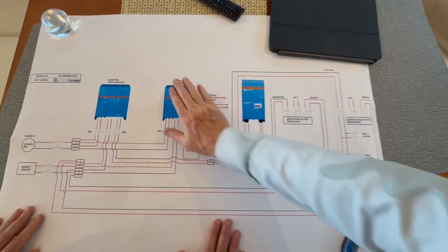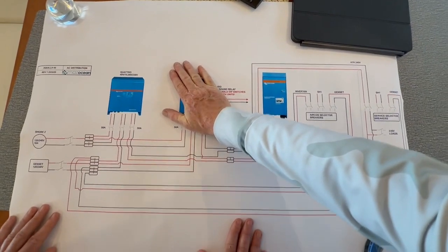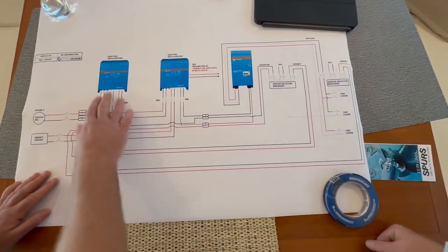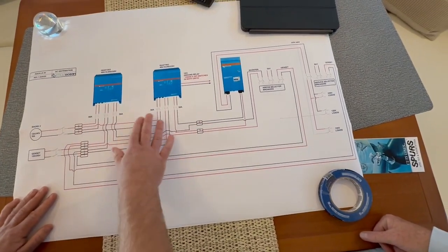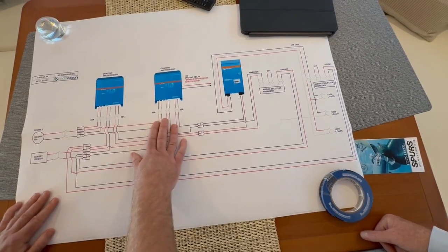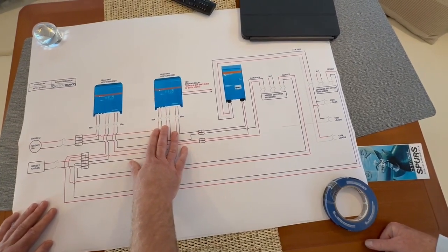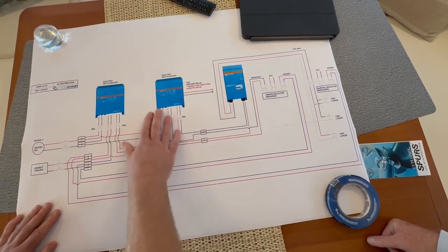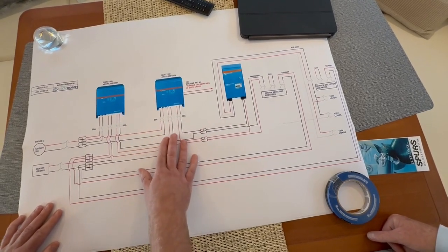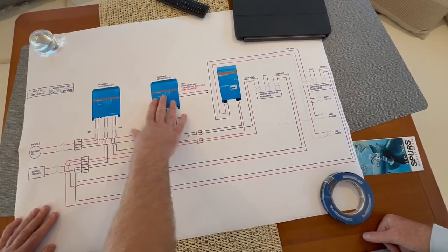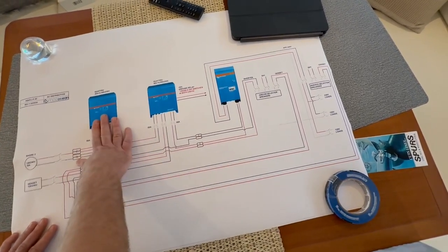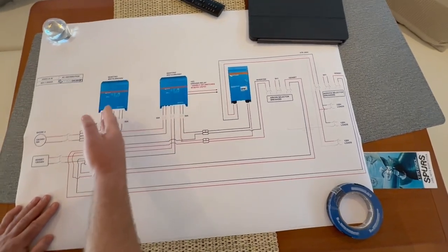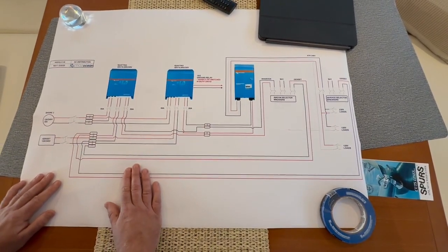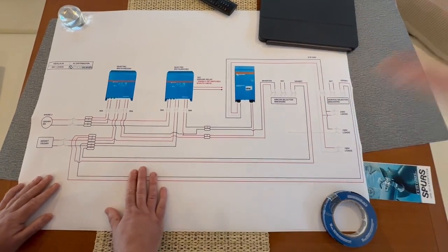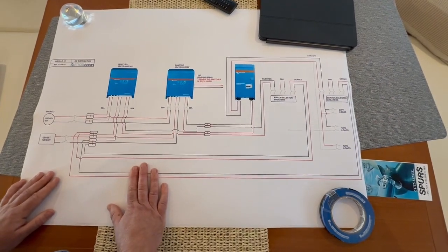Now, what happens if one Quattro goes down? In this situation, because they are paralleled together, it will ultimately cause the entire system to shut down. You can, with programming - plugging in with a laptop - disable one and set things up to operate off just one, but you're only going to have 10,000 watts, or 10 kW, of inverted power.